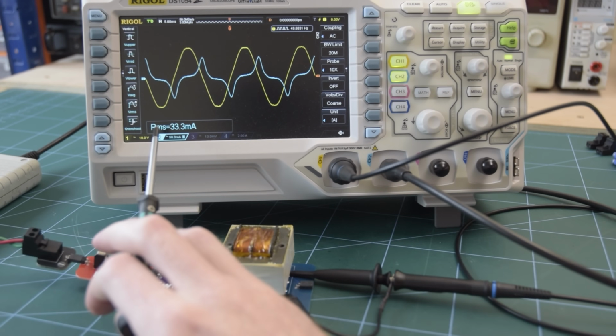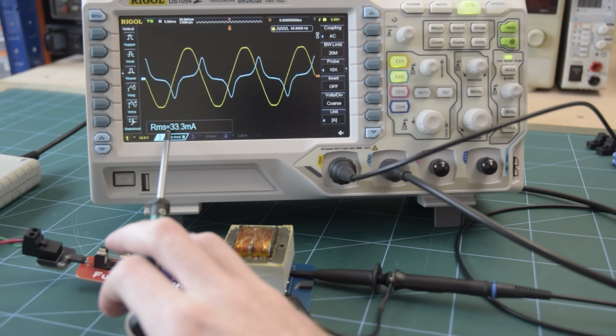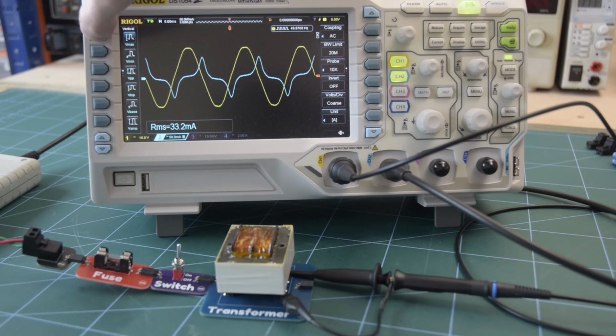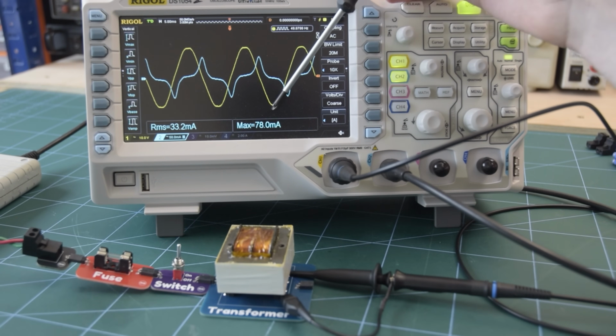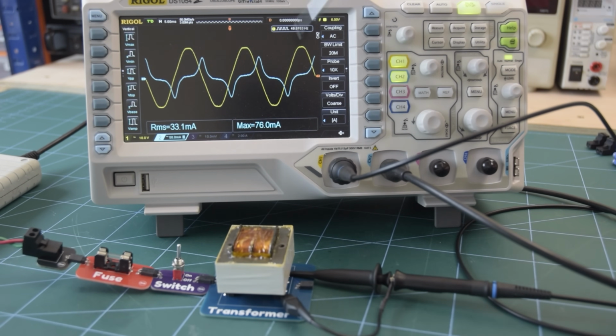I've added a measurement for the RMS current, and it says 33 milliamps, about the same as what we got from our clamp meter earlier. Although we can also see the maximum or peak current is almost 80 milliamps because of this saturation.